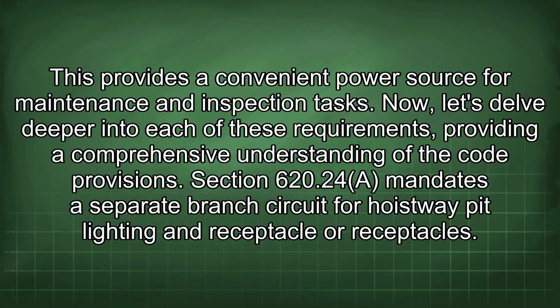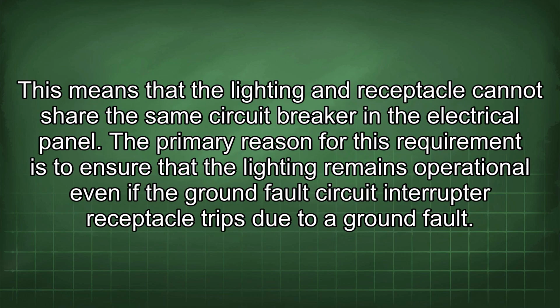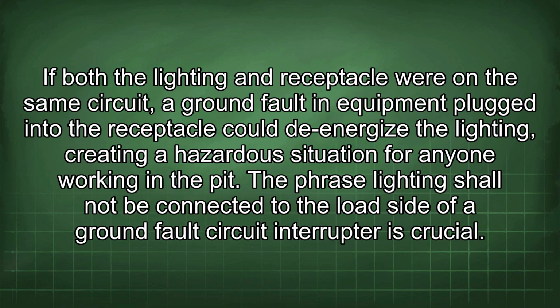Section 620.24 mandates a separate branch circuit for hoistway pit lighting and receptacle or receptacles. This means that the lighting and receptacle cannot share the same circuit breaker in the electrical panel. The primary reason for this requirement is to ensure that the lighting remains operational even if the ground fault circuit interrupter receptacle trips due to a ground fault. If both the lighting and receptacle were on the same circuit, a ground fault in equipment plugged into the receptacle could de-energize the lighting, creating a hazardous situation for anyone working in the pit.